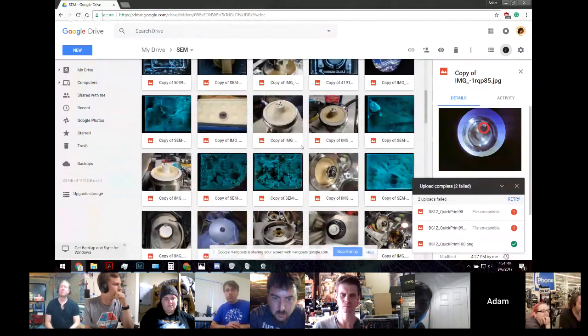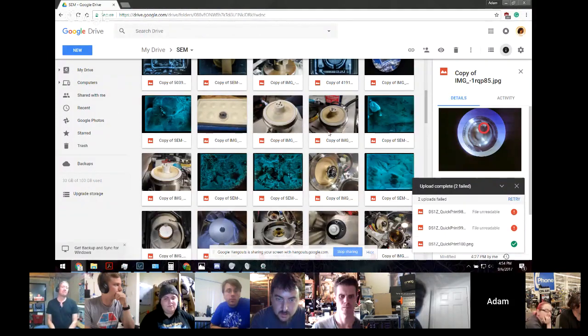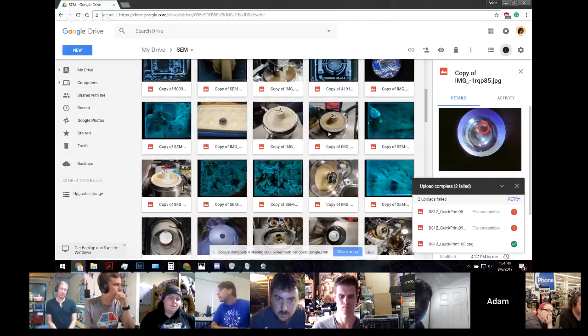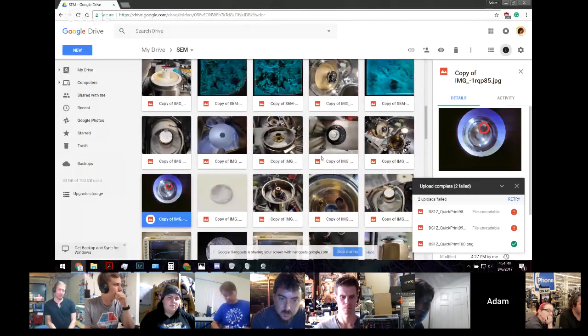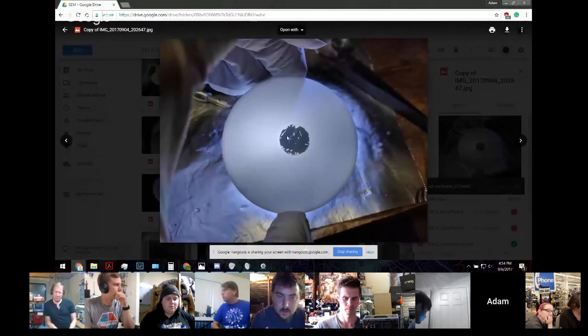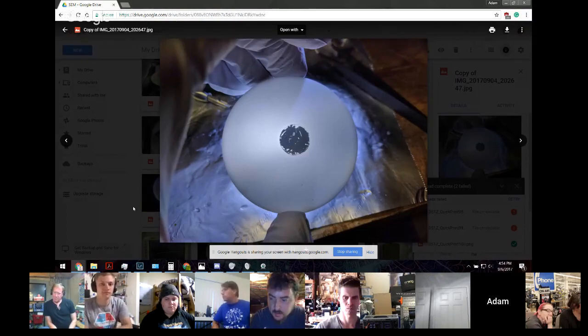Everything was going well, and then the scintillator needed to be changed as well. So that's just a lot of failures this week. The scintillator is fundamental to the way the electron microscope works. It's what converts the electrons into photons for the microscope to actually generate an image from those photons. And my scintillator was looking like this. This should be a perfectly uniform disc, and it's not, which tells you just how horrible it got.